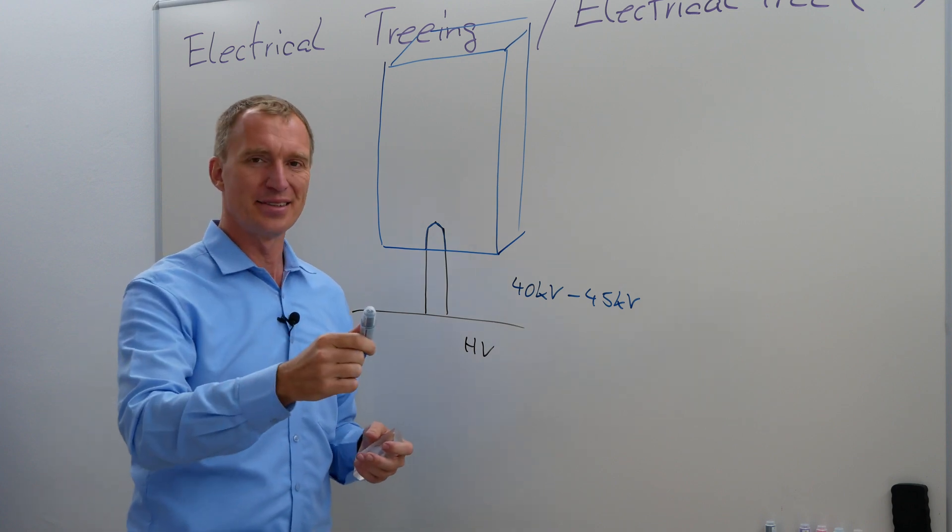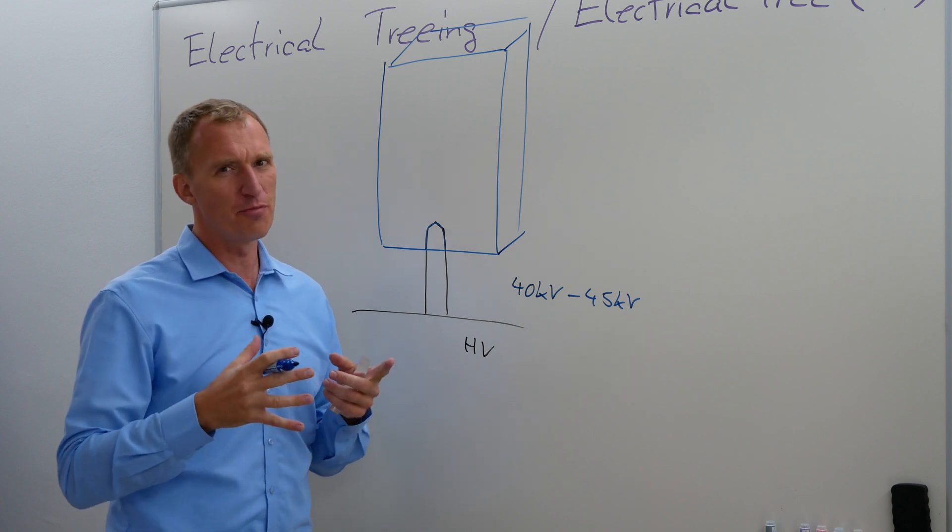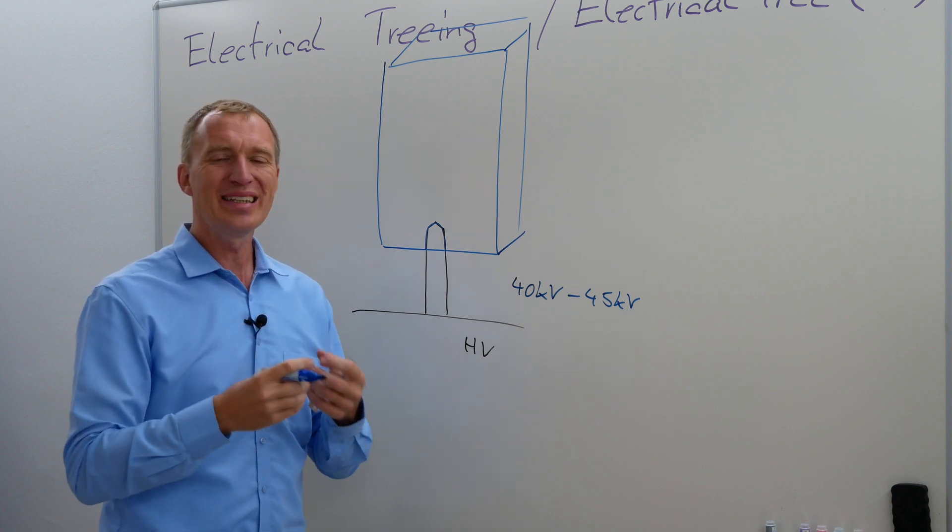And now we hoped for electrical treeing to start, and it didn't. And the reason is, very often in order to have partial discharges starting, we need air.